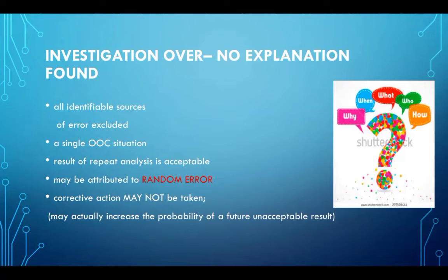Now we have checked everything. We detected a problem. We checked our control material, we checked our calibrator, we checked our reagent, we checked our instrument hardware, we checked environmental conditions. We have also checked requirements related to the operator. But sometimes still there is no identifiable cause, but definitely there is an out of control situation.